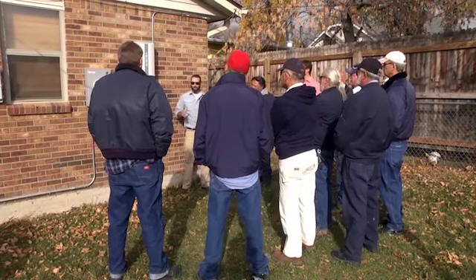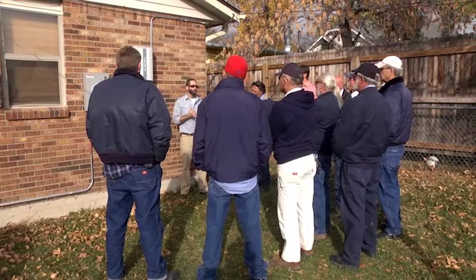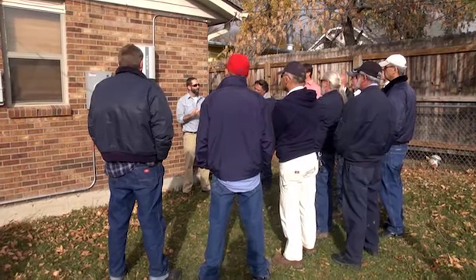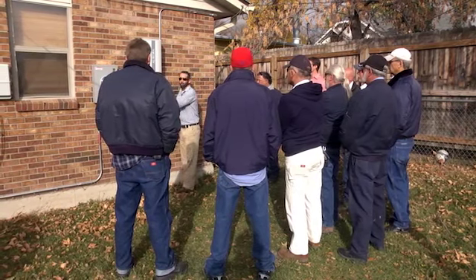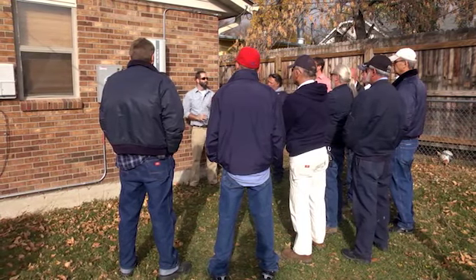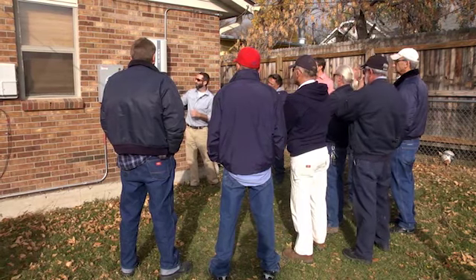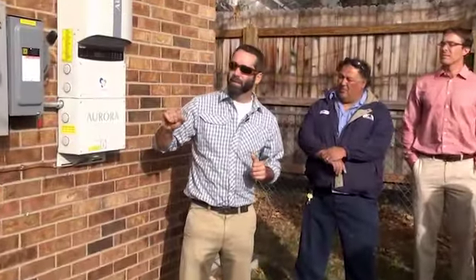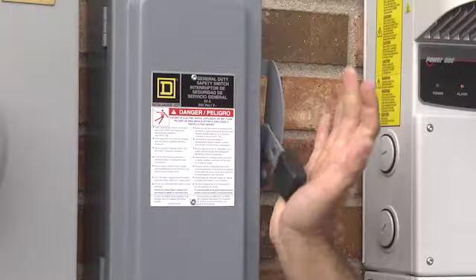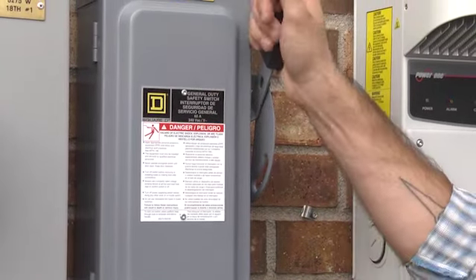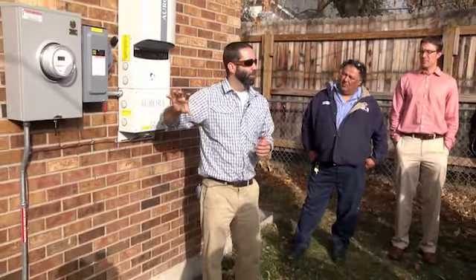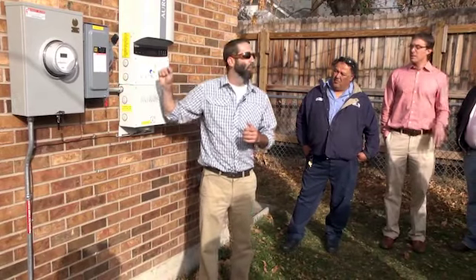So the interesting thing is, depending on how we interconnect at the house, whether it's a backfed breaker or a supply side tap or a line side tap, these two pieces of equipment are always right here. So that's the most critical thing. They're always there. So now you can hear it clicking and starting up again. In some cases, in this unit in particular, there's an exterior main disconnect. In a lot of the houses in the dispersed areas, there's no main exterior disconnect. There's just a meter that then feeds into a split bus panel. It's usually in the kitchen. So we're actually interconnecting inside, and we have a box just like this that's inside as well. That's in addition to this box. This box will still always be here.